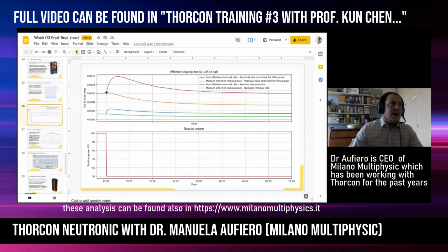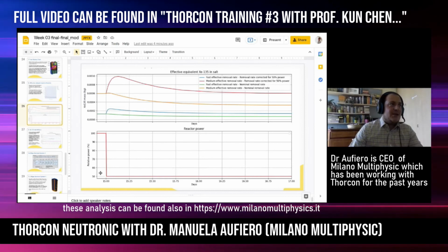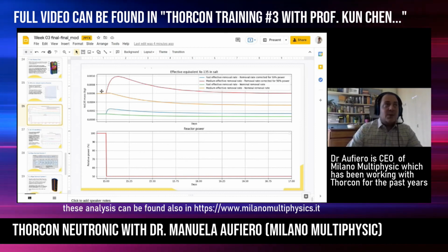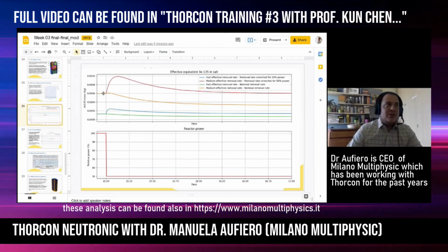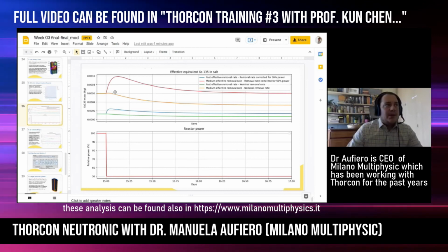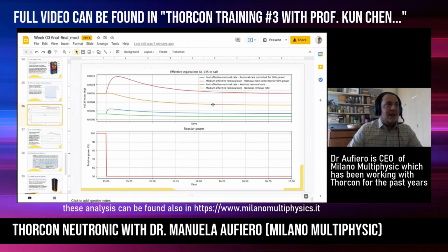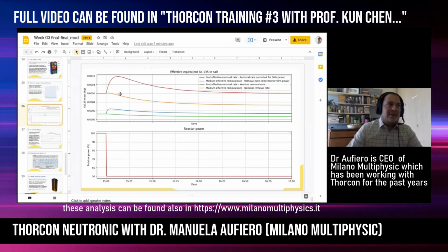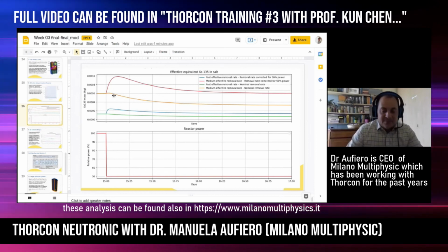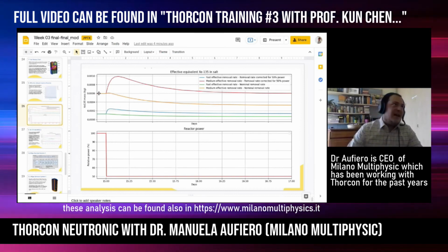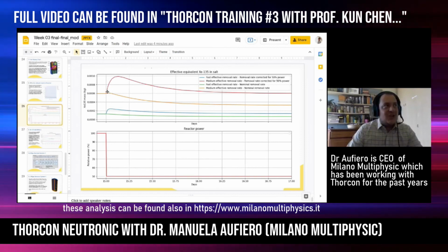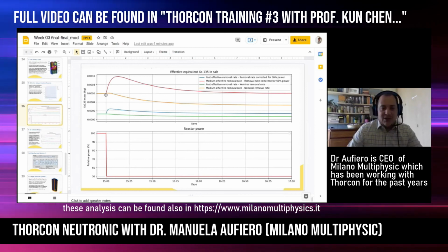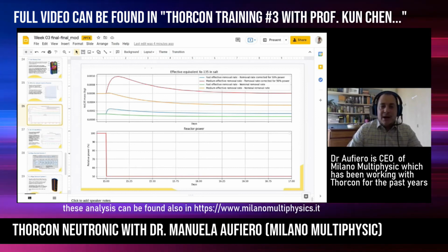So if we drop the power instantaneously from 100% to 50%, and we keep removing xenon with the same effective rate we were assuming for the steady state operation in 15 days, slowly the system adapts to the new level of xenon decay rate coming from a reduced level of iodine production. You can barely see a slight increase here at the beginning. This is due to the minor fraction of xenon atoms that are removed by neutron capture.